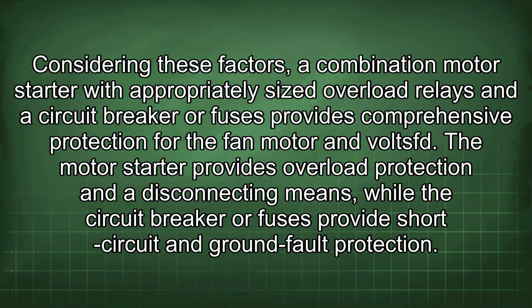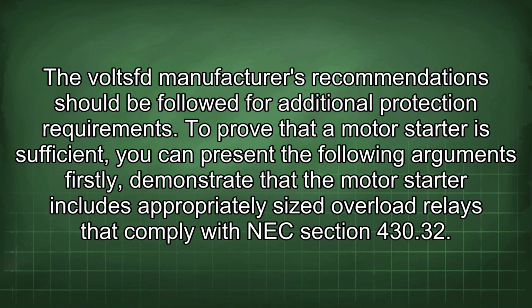protection for the fan motor and VFD. The motor starter provides overload protection and a disconnecting means, while the circuit breaker or fuses provide short circuit and ground fault protection. The VFD manufacturer's recommendations should be followed for additional protection requirements. To prove that a motor starter is sufficient, you can present the following arguments.